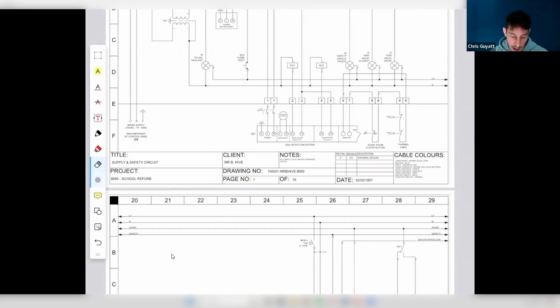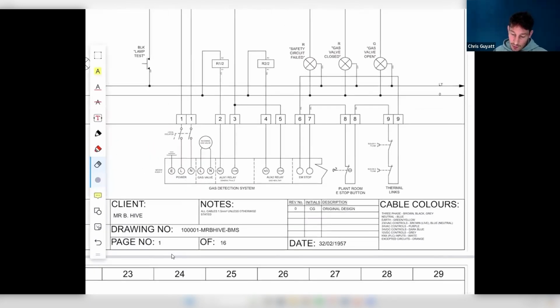So the scenario was: you're on site installing and commissioning the system, and the client has asked for a last-minute change - would it be possible to have an e-stop in the reception area? So the receptionist, if she feels there's a problem - maybe hearing noises and isn't sure of something - she just wants to be able to hit the e-stop and it shuts the system down. Now in a real project it's probably unlikely the plant room would be within 20 meters of the reception area, but just play along with me here. So that's the idea behind this scenario - we want to add an additional e-stop to our system but still have exactly the same operation.